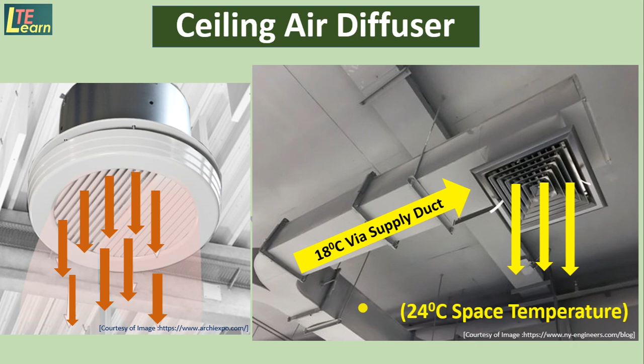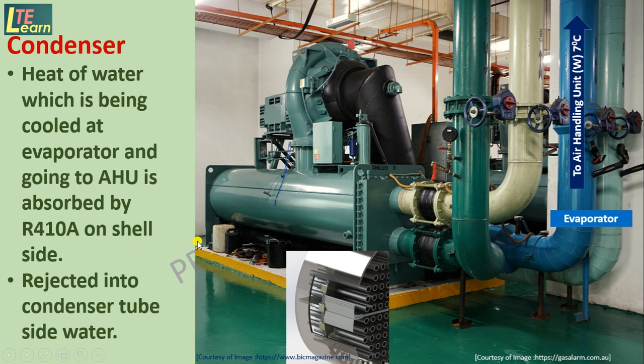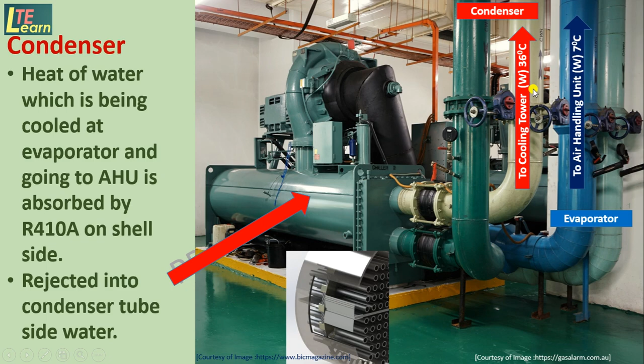In the condenser, the heat of the water which is being cooled at the evaporator, the chilled water which is going to the air handling unit, is absorbed by the refrigerant R410A on the shell side. So this heat absorbed from the chilled water by the refrigerant is rejected into the condenser tube side, which carries water as a cooling medium. So this water gets warm. This warm water at 36 degrees Celsius goes to the cooling tower for heat rejection to the atmospheric air.